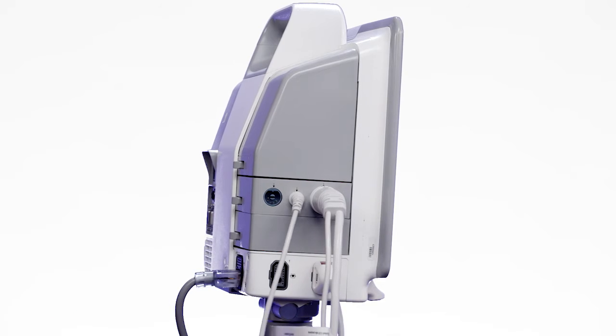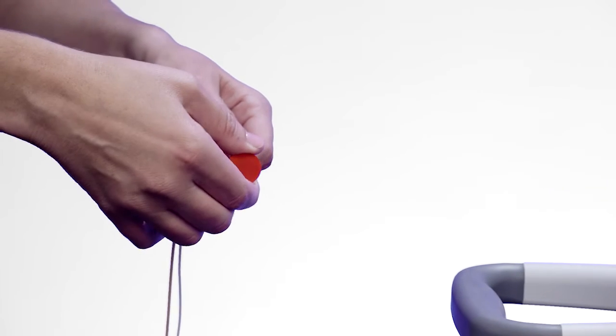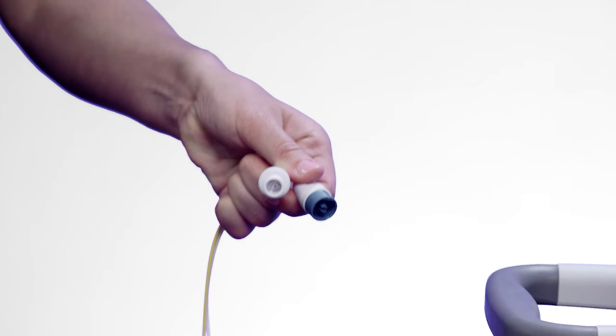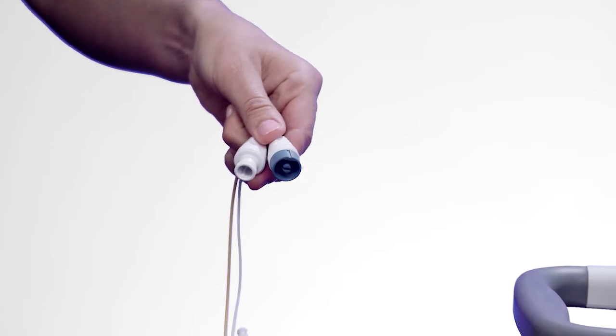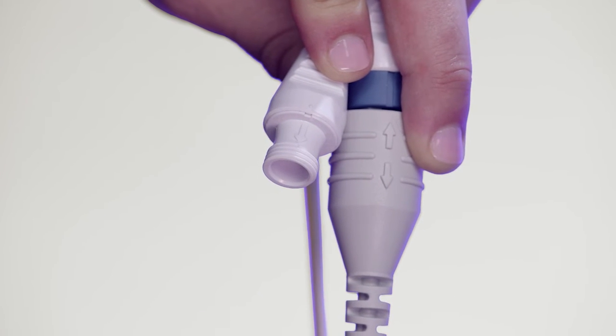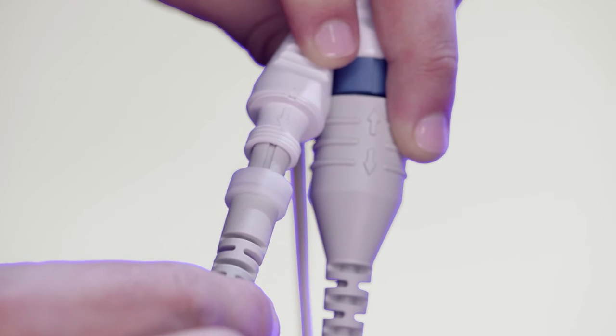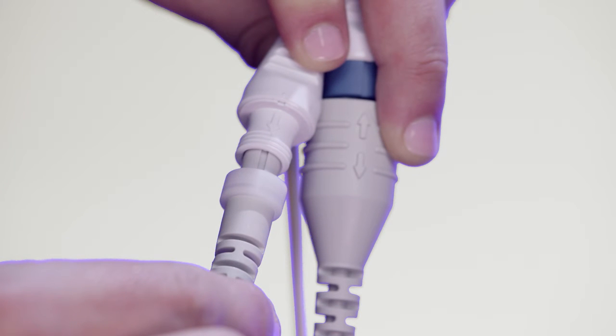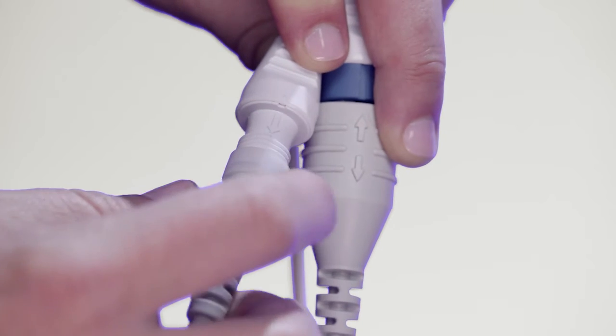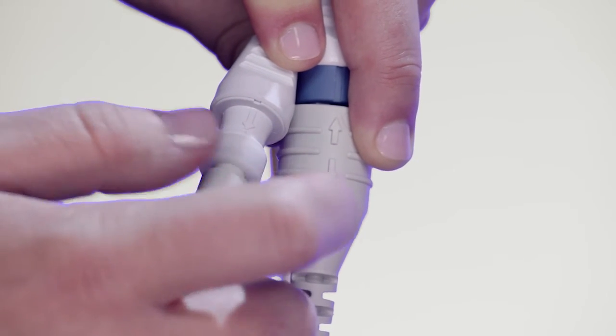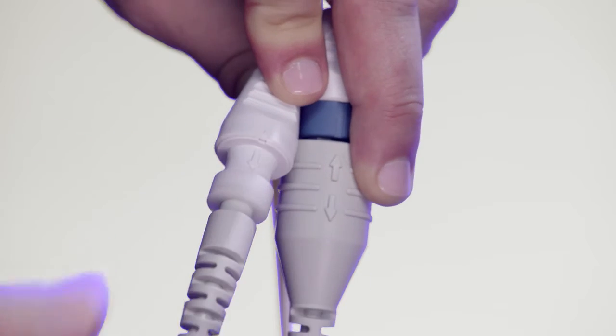Disconnect the thermistor and thermal filament connectors from the HemoSphere Swan-Ganz module. Locate the 2 red-capped ports on the Swan-Ganz catheter. Remove the caps and connect the ports to the thermistor and thermal filament connectors on the CCO cable by matching the blue port with the blue connector and the white port with the white connector. Note that when you connect the white thermistor connector to the thermistor port, the arrow on the port should be aligned with the notch on the connector prior to insertion. Once properly seated, twist the locking ring on the thermistor connector to secure the connection.